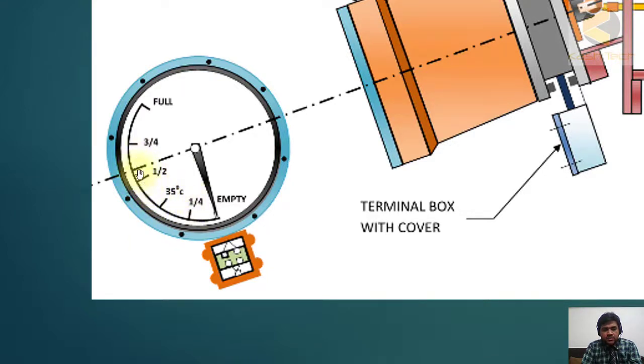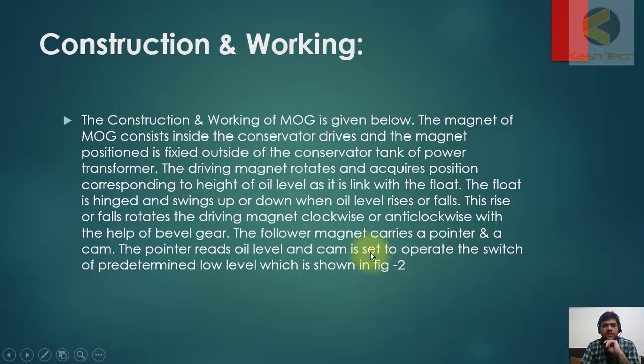Construction and working of MOG is given below. The magnet of the MOG consists inside the conservator drive, and the magnet position is fixed outside of the conservator tank of power transformer. The driving magnet rotates and acquires position corresponding to height of oil level as it is linked with the float. The float is hinged and swings up or down when oil level rises or falls.